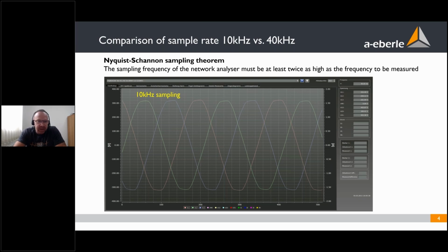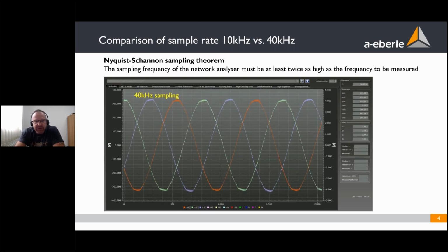And to show one example, I've made a measurement in a low voltage grid and we get some interference with superharmonics. I make an oscilloscope snapshot with an old PQBox 100, and the PQBox 100 is working with a sampling frequency of 10 kilohertz. So we see a perfect sinus without any disturbances. I make the same snapshot with the PQBox 200, and here we are working with a sampling frequency 4 times higher, with 40 kilohertz. And with 40 kilohertz, you see a ripple over the fundamental frequency.